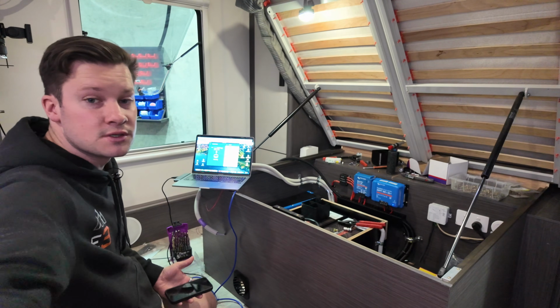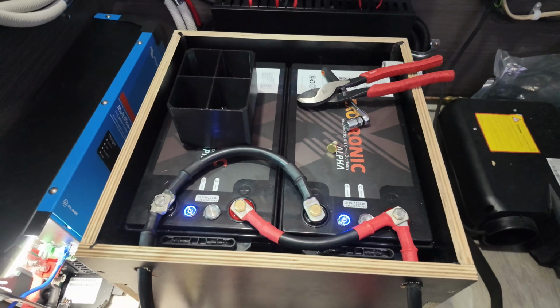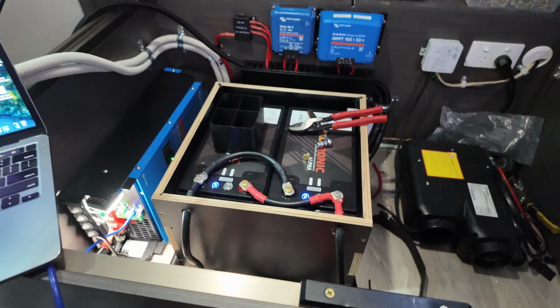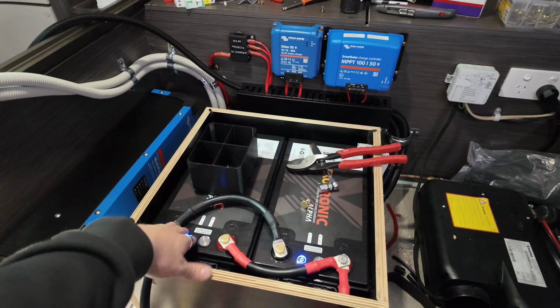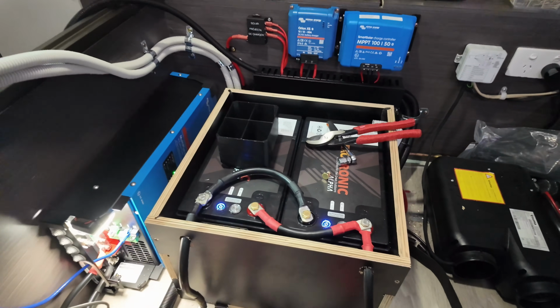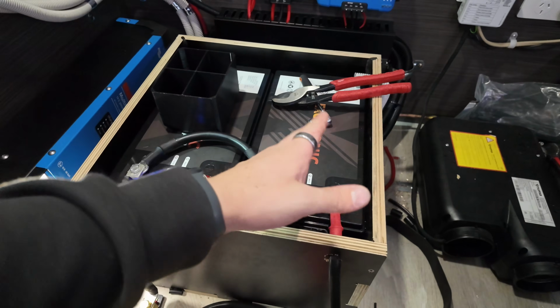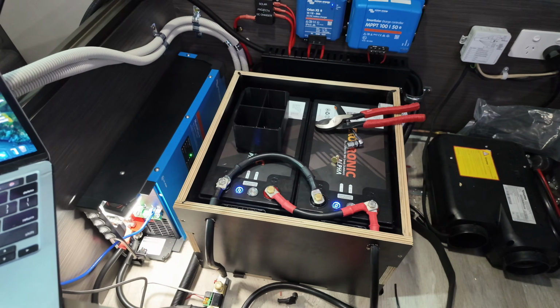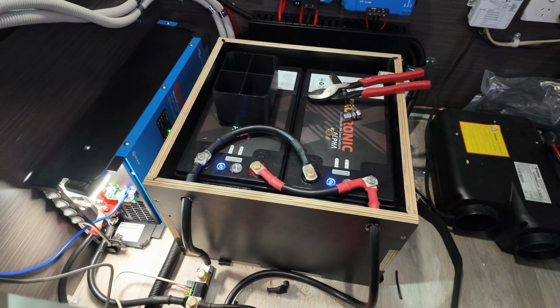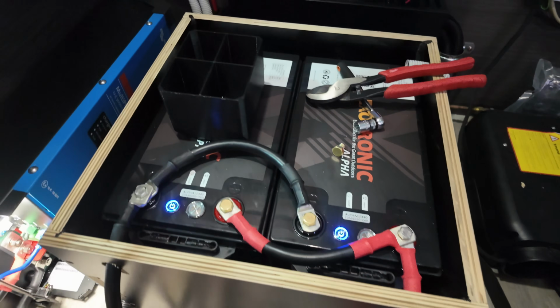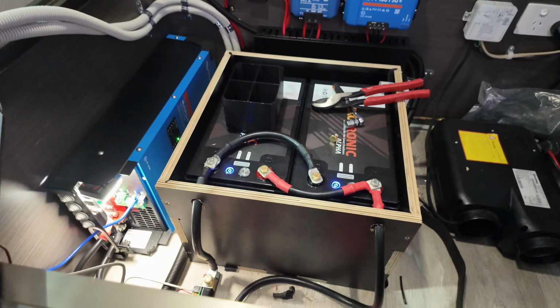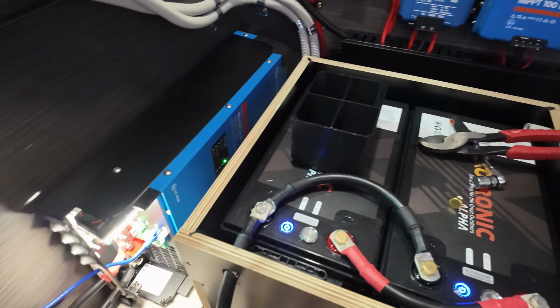We've got the batteries now in the box, wired up. What we've done here is active off this battery, neutral off the other battery, so that you don't get imbalances with your battery percentage if the neutral comes off the same battery as the active - we keep them like that. Essentially it's all one battery cell, and the active balancer in each battery works to make sure all 4 cells in each battery are balanced. I'm just going to program these up and then we'll get on to pretty much the final bit.